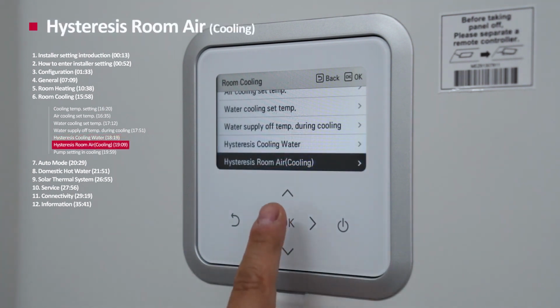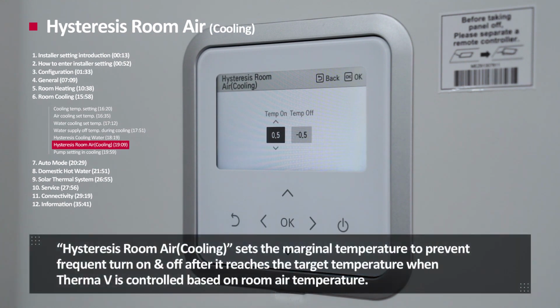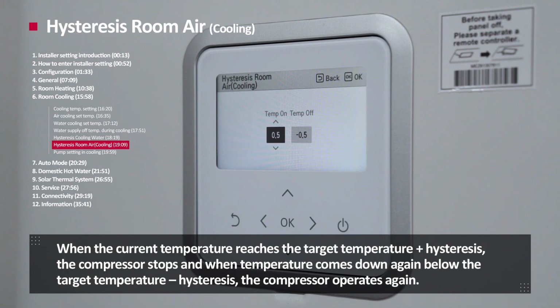Hysteresis, room air cooling. Hysteresis room air cooling sets the marginal temperature to prevent frequent turn on and off after it reaches the target temperature when Therma V is controlled based on room air temperature. When the current temperature reaches the target temperature plus heat statuses, the compressor stops. And when temperature comes down again below the target temperature minus heat statuses, the compressor operates again.